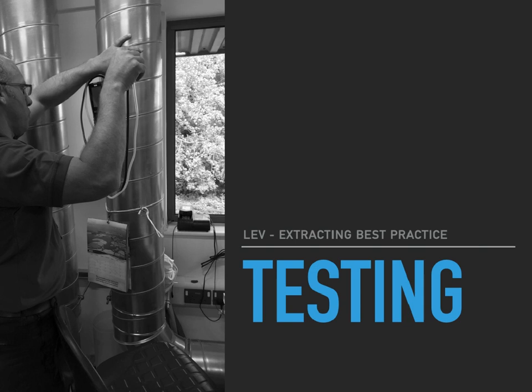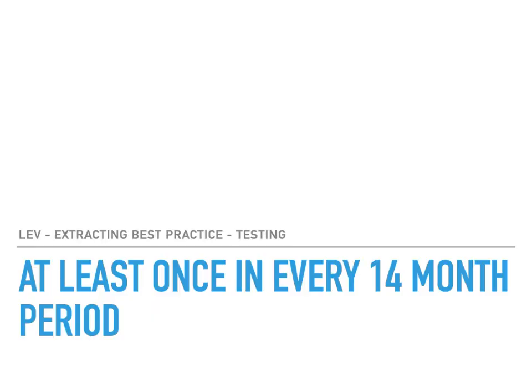often referred to as the annual test, or LEV test, or COSHH test - people call it all sorts of things. But it's not always an annual test. Again, the law is quite clear on this. It does say most systems need to be tested at least once in a 14-month period, but it also says unless they appear on Schedule 4.